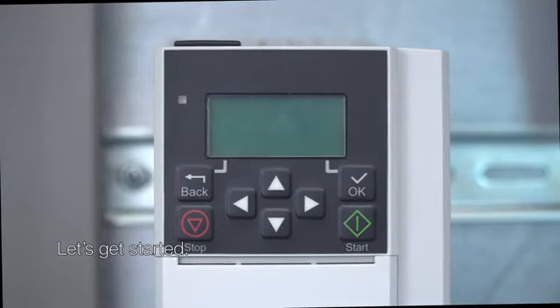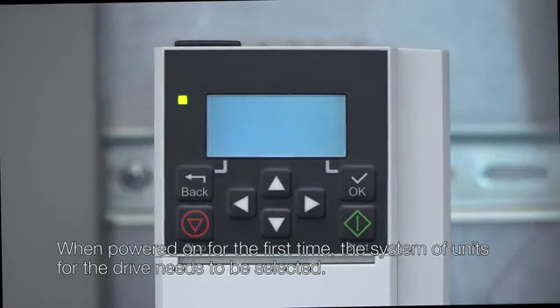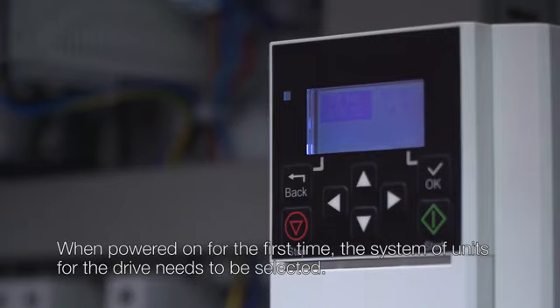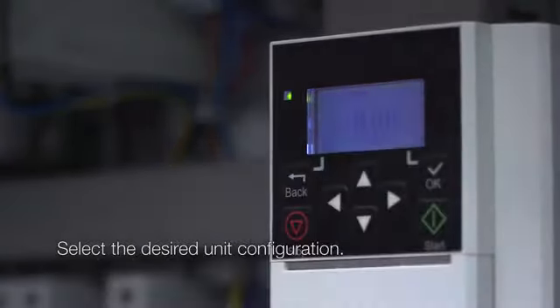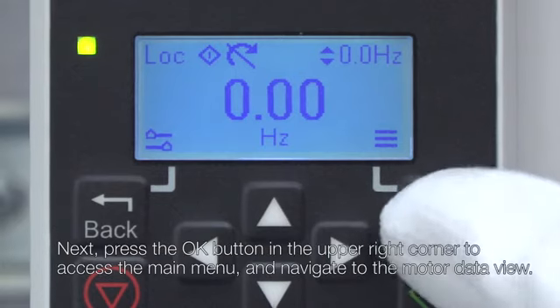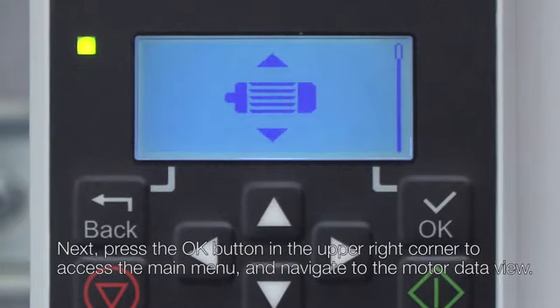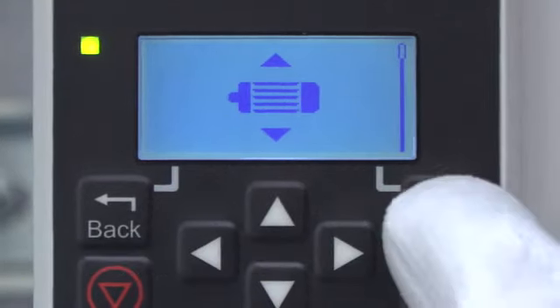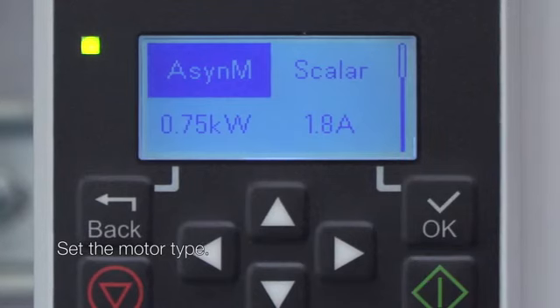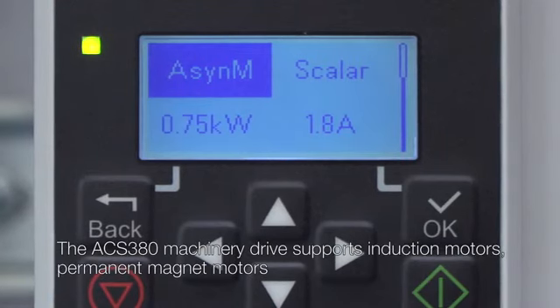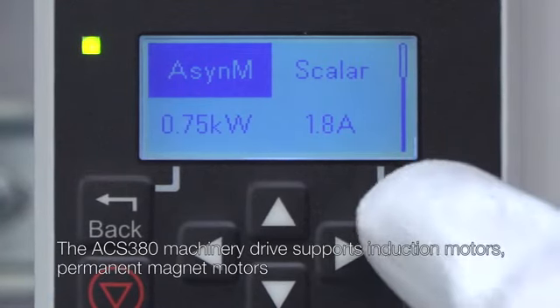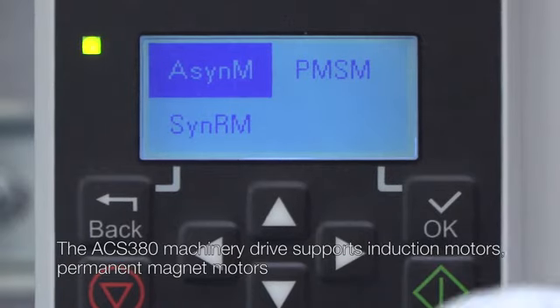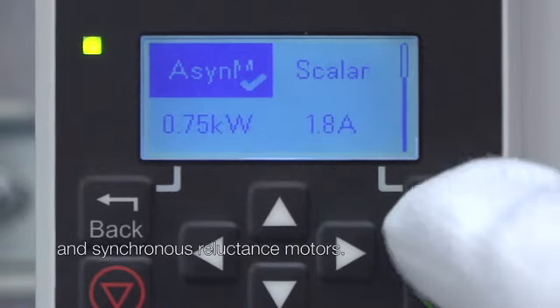Let's get started. When powered on for the first time, the system of units for the drive needs to be selected. Select the desired unit configuration. Next, press the OK button in the upper right corner to access the main menu and navigate to the motor data view. Set the motor type. The ACS380 machinery drive supports induction motors, permanent magnet motors, and synchronous reluctance motors.